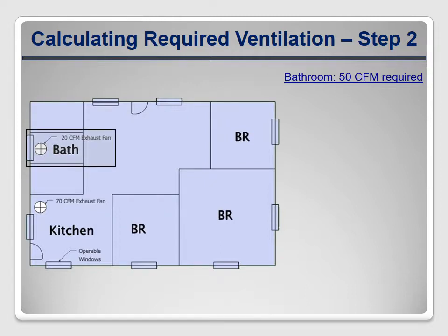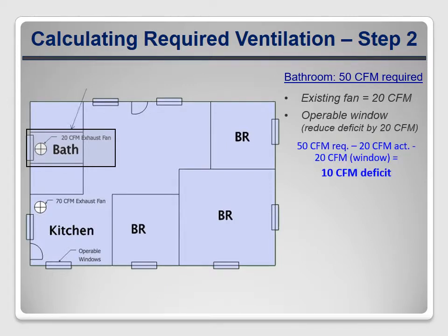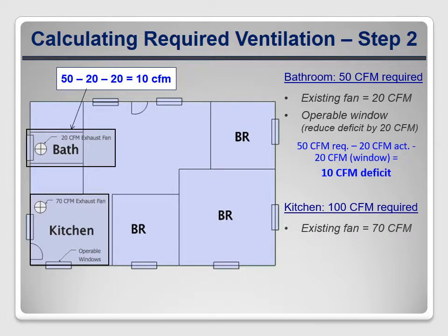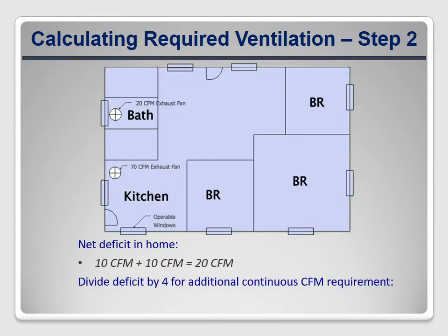Each full bath requires 50 CFM but gets credit for existing fans and operable windows. The existing bath fan provides only 20 CFM, and since there's an operable window, we add a 20 CFM credit — resulting in a net deficit of 10 CFM. The kitchen requires 100 CFM but the existing fan provides only 70. Again, we get a 20 CFM credit for an operable window — note that there are two windows in the kitchen, but you only get one window credit per room. So the net deficit is also 10 CFM for the kitchen. Adding the two deficits: 10 + 10 = 20 total CFM. Since the fans are intermittent, we divide by four: 20 ÷ 4 = 5 CFM exhaust deficit.